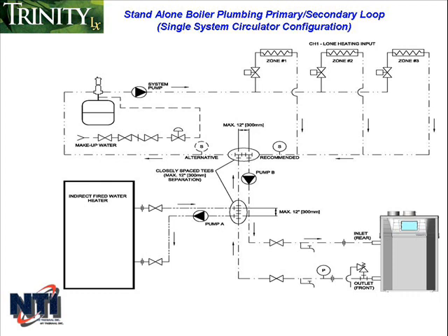One thing to remember when using the supplied strap-on sensor to modulate to the system temperature is that strap-on sensors typically register a lower than actual water temperature in the pipe. To offset this, we recommend reducing the maximum central heating set point by 10 to 15 degrees and insulating around the installed system sensor. Without doing this, you run the risk of having higher than anticipated water temperatures.